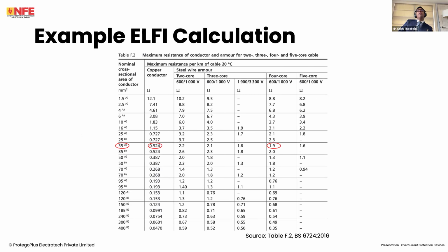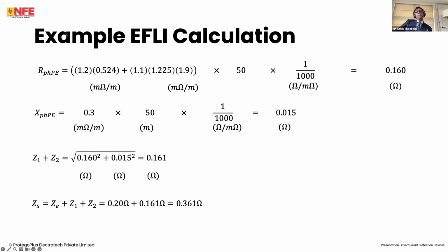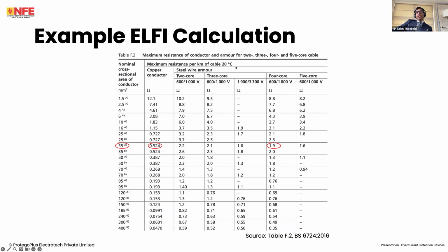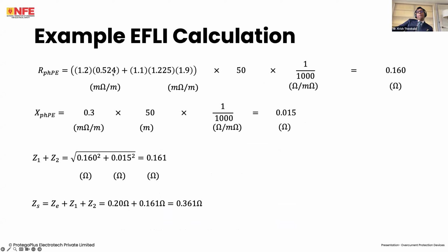Okay, now, how do we come up with the resistances? 35 square mm copper conductor is 0.524 milliohms per meter. Steel wire armor, 4-core cable. Resistance of the armor is 1.9 milliohms per meter. Okay. Now, you will notice that these resistances are at 20 degrees Celsius. However, when the cable runs at maximum operating temperature, the resistances are higher because of the temperature. So there are certain correction factors taken into account. 0.524 milliohms per meter is the value for the core. We multiply this by 1.2 to get the 70 degree value.